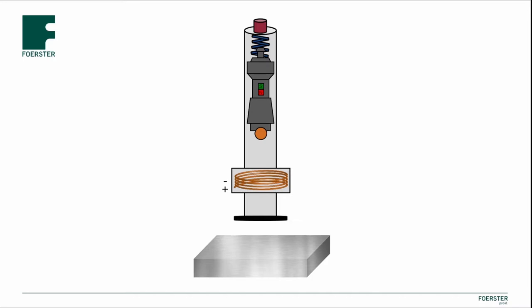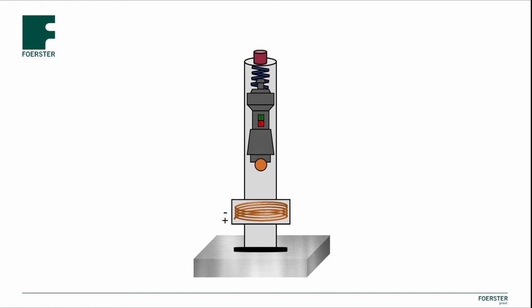The operating principle of the Leeb rebound method is to accelerate an impact body with a defined energy against the surface of the material to be measured. The impact body is equipped with a tungsten carbide ball on the front end and an integrated permanent magnet in the center. The impact energy is generated by a spring system located in the shaft of the impactor.